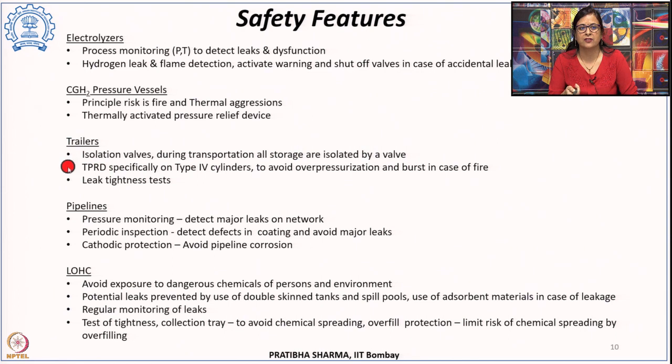These are equipped with independent valves, so that during transportation, all these storage tanks are isolated by a valve. Also, these trailers have thermally activated pressure relief devices, especially when the loaded tanks or cylinders are type 4 tanks, so as to avoid any kind of overpressurization or burst in case of fire. And these are located on the top and pointing towards the sky, so that if there is any release, that should go up very fast. Then there are different leak tightness tests which are performed before these trailers start their journey.